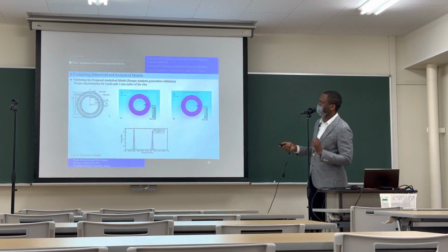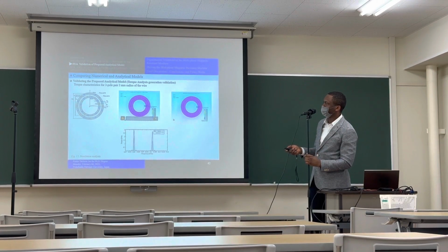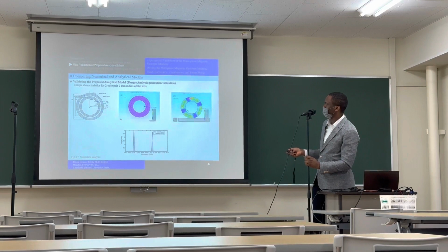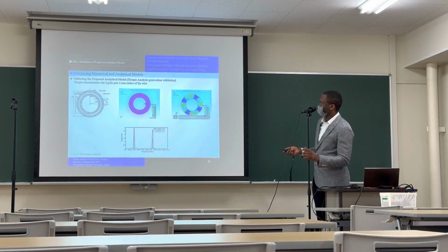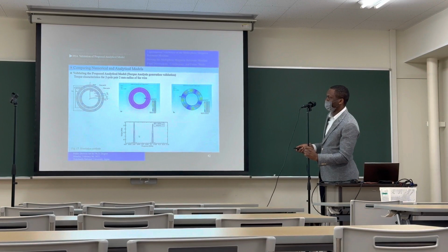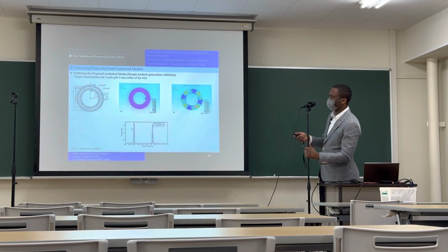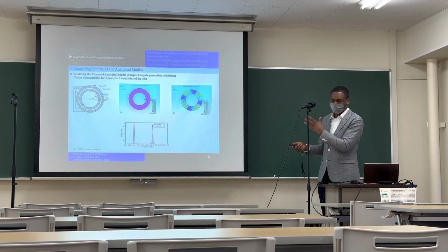Then, an example is, let's say we use a 2-pole pair machine like this. We follow the same process, and the first stage is, you see, this is the machine now in motion, when all the stages that we described above are followed. At the end of the day, we have two torques. We have the torque that we can determine analytically for the same configuration of the machine, and then we have the one that is done through finite analysis, and we try to compare it. We realize that, of course, they lie within the same bandwidth, but the torque response of the finite analysis is higher than the one determined analytically. You still have to correct this.